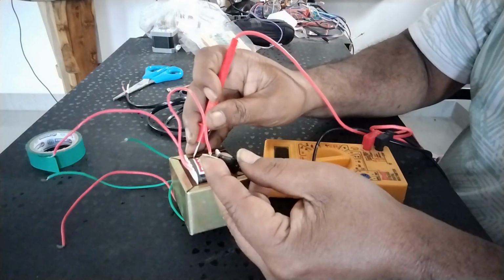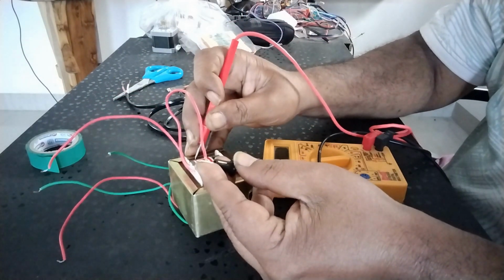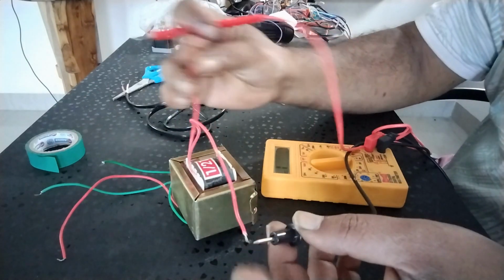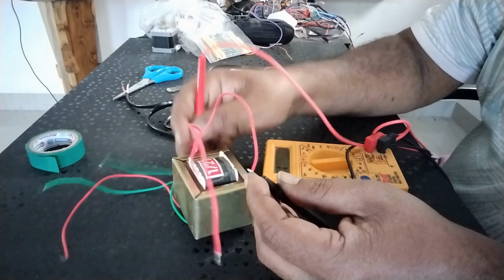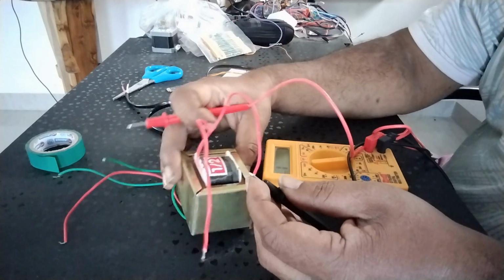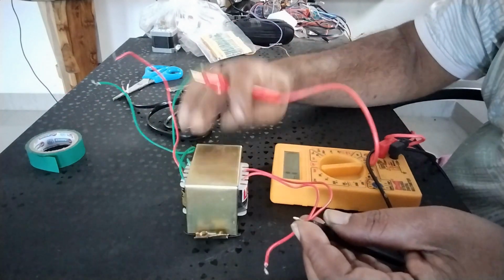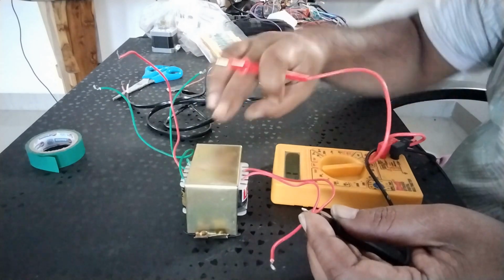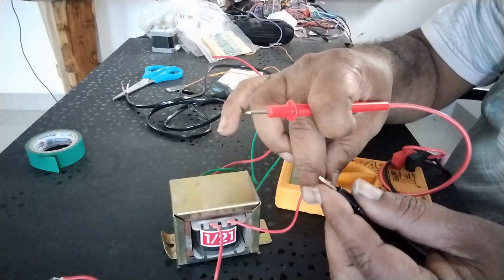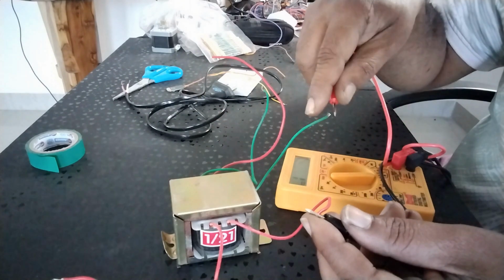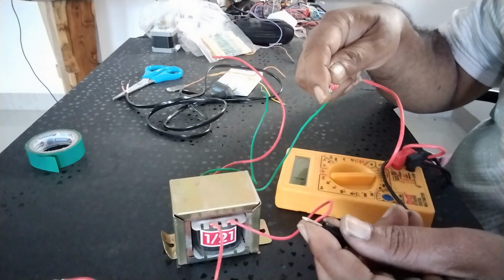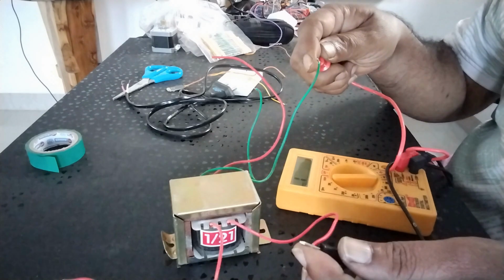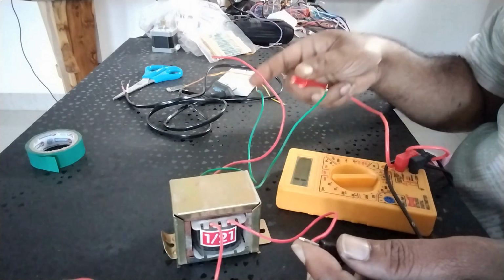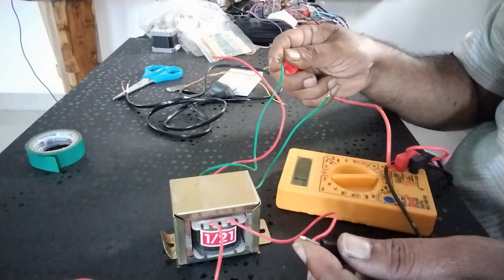Check for high voltage leakage to the core, to ensure there's no dangerous voltage seepage from the primary winding to the transformer's core. Connect one probe of the multimeter to one terminal of the primary winding and the other probe to the transformer's metal core. If the multimeter does not beep, there is no leakage, and this part of the transformer is safe. Repeat this test with the other terminal of the primary winding. If you hear a beep during either test, it indicates high voltage leakage to the core, which is extremely dangerous. Do not use the transformer in this condition.